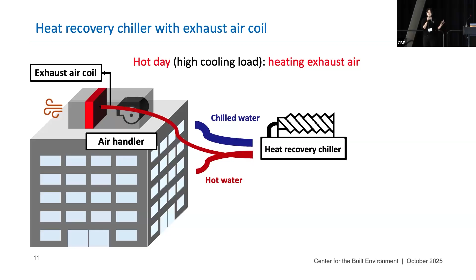So let's see how this exhaust air coil load behaves with our measured data. This graph illustrates the relationship between outdoor air temperature and the exhaust air coil load. The blue dots indicate exhaust air coil load under heat recovery mode, when the air is cooled, and the red dots indicate exhaust air coil load under heat rejection mode, when the exhaust air is heated. And the coil switches between the 2 modes at around 55 degrees Fahrenheit. And the coil load increases as the outdoor air condition becomes either hotter or colder.